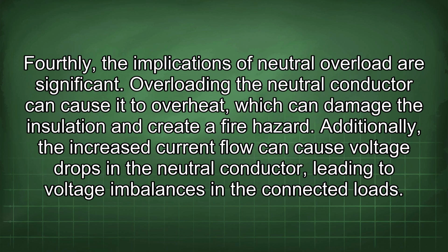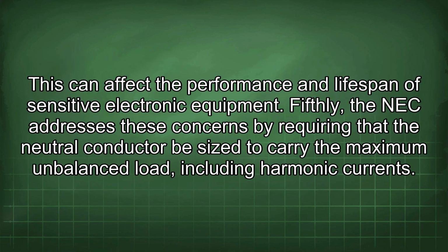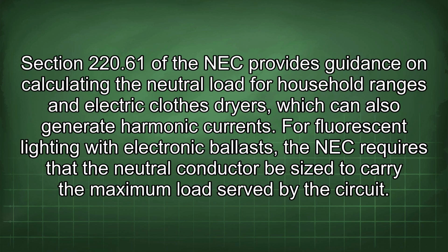Fourthly, the implications of neutral overload are significant. Overloading the neutral conductor can cause it to overheat, which can damage the insulation and create a fire hazard. Additionally, the increased current flow can cause voltage drops in the neutral conductor, leading to voltage imbalances in the connected loads. This can affect the performance and lifespan of sensitive electronic equipment. Fifthly, the NEC addresses these concerns by requiring that the neutral conductor be sized to carry the maximum unbalanced load, including harmonic current. Section 220.61 of the NEC provides guidance on calculating the neutral load for household ranges and electric clothes dryers, which can also generate harmonic currents.